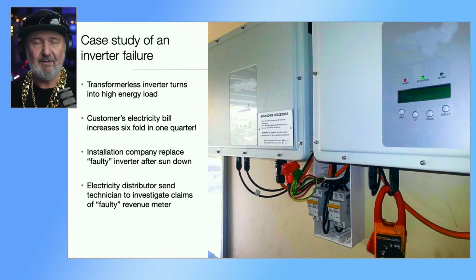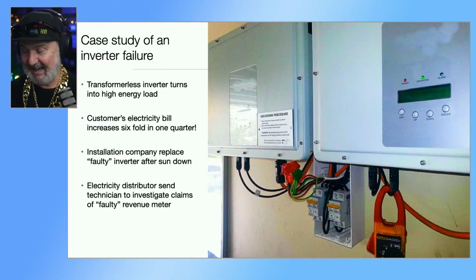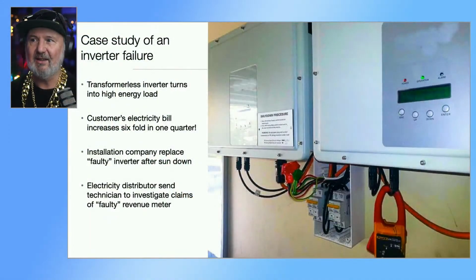But the customer, after having this system installed, noticed their bill went up sixfold. Sixfold. Can you imagine the look on their face when they got their bill? Their bill was normally $200, I think it was a quarter, so they were a very low energy user, and it went to $1,200. They just about fell off their chair. So the customer complained and they did actually notice at the time that one of the inverters had a red light on it and it was warm to touch day and night.